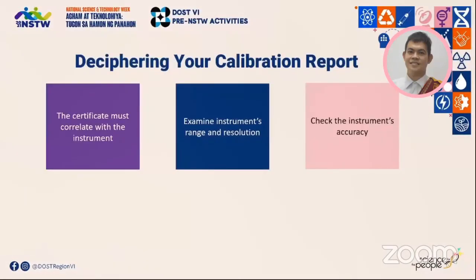The instrument's range and resolution must be examined to see whether these fulfill the measurement requirements. For example, to make a weight measurement of 160.5 grams, the range of the measuring instrument should cover 0 grams to around 200 grams, and the resolution should be 0.1 grams. The next parameter to be checked is the instrument's accuracy. The accuracy of the instrument, or the maximum error reported on the certificate, should meet the specified required accuracy of the measurement.